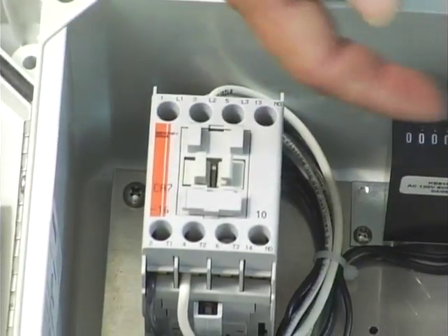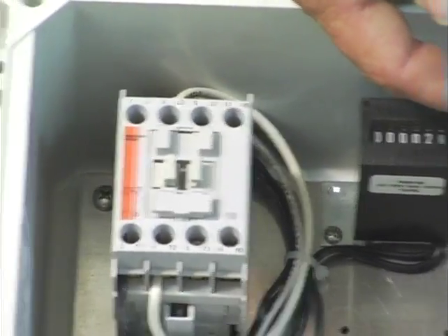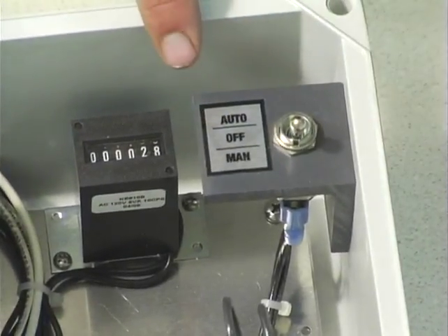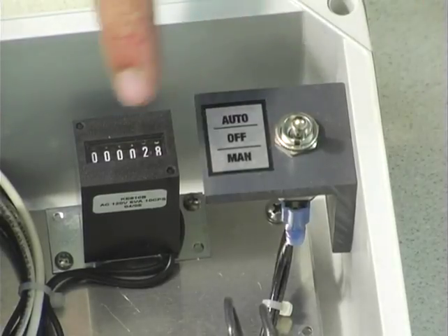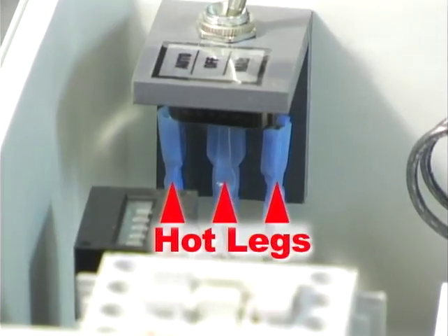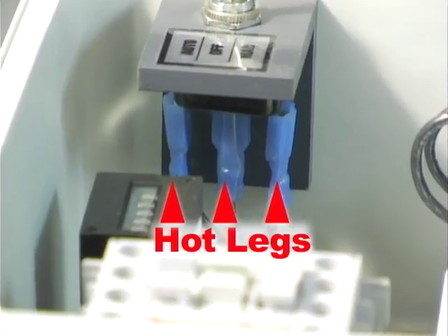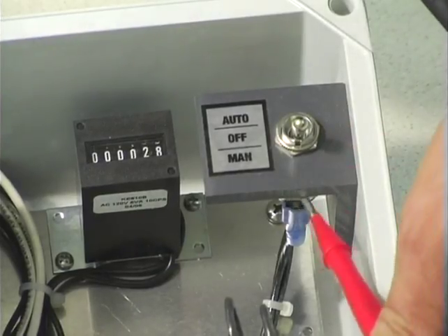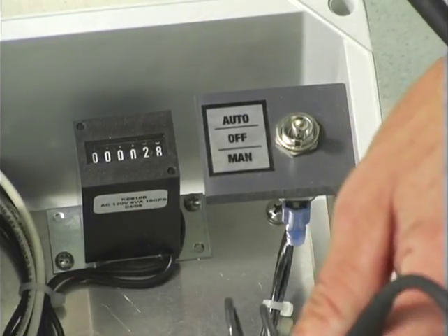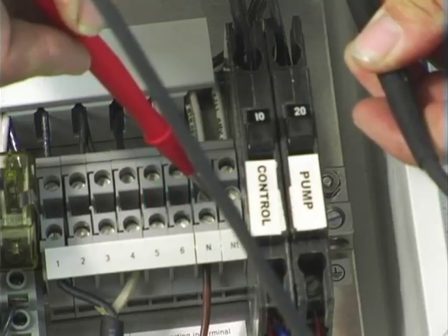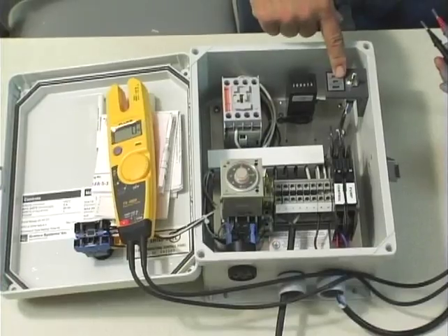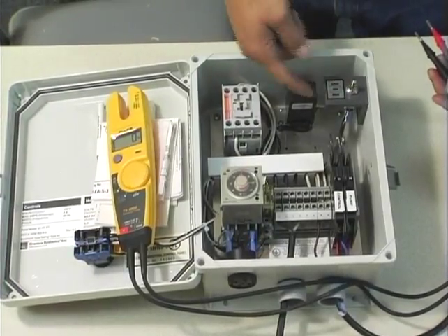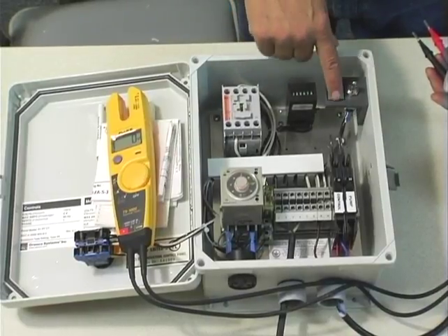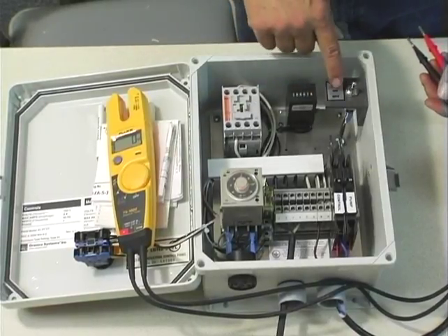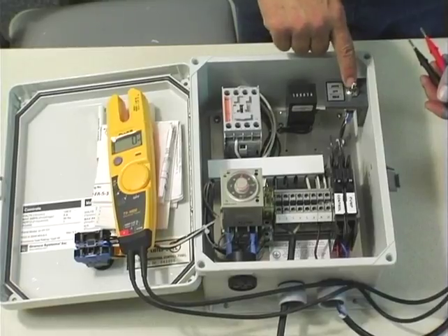You can test the back side of the manual off auto switch with your probes again to neutral. These are only hot legs on the back side of here, so what you'll do is you'll take one of the leads, touch it on each of the terminals, the other lead will go down to the neutral bar. When we metered the electricity from the hand-off-auto switch to the neutral bar, it was determined that it was a faulty switch.